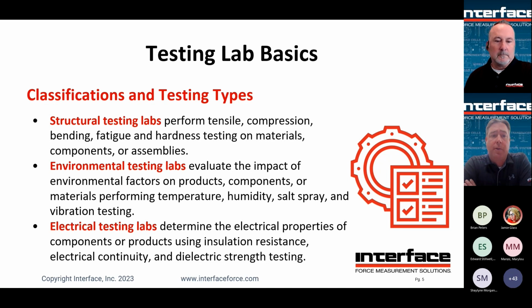Environmental testing labs, they're looking for the impact of environmental factors on the same kinds of products and components, validating performance over temperature, perhaps in humid environments, salt spray environments, up to and including vibration testing. Electrical testing labs, these guys are qualifying different electrical components by verifying their electrical properties, checking for insulation resistance, continuity, dielectric strength, those types of things, up to and including certifying for perhaps hazardous environments.